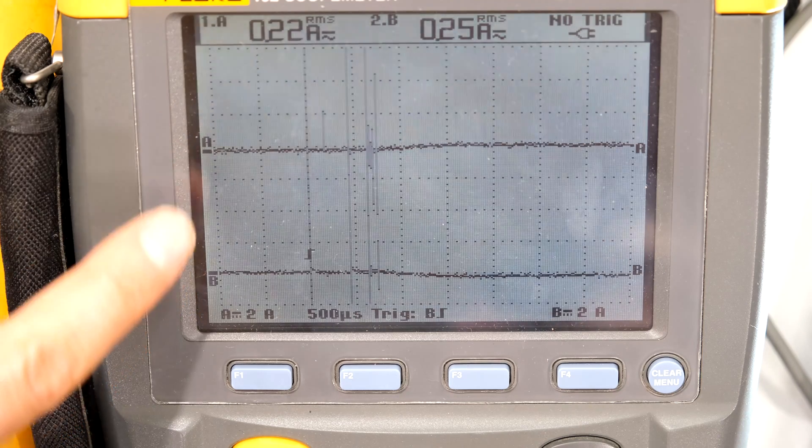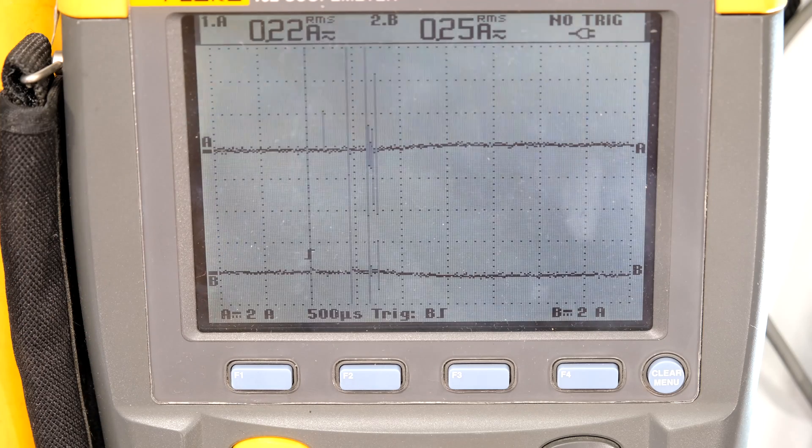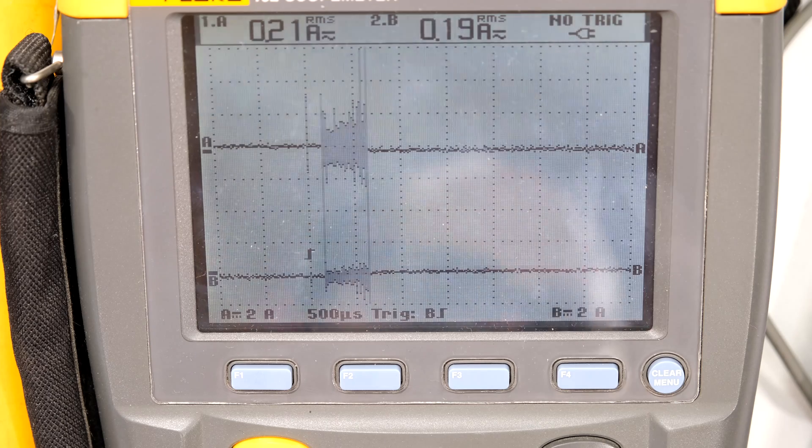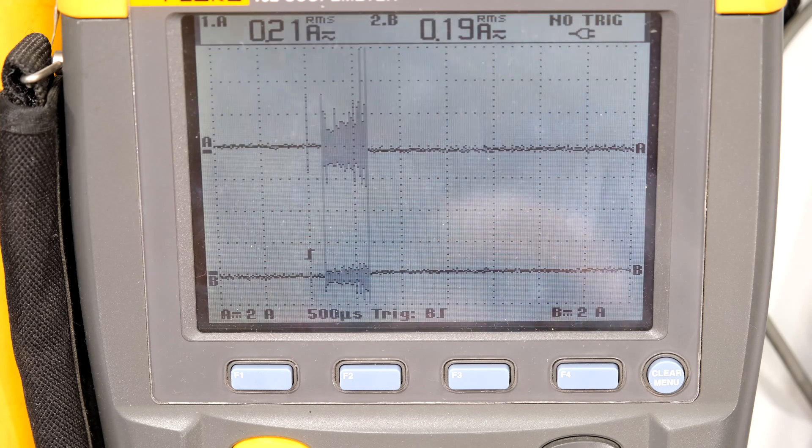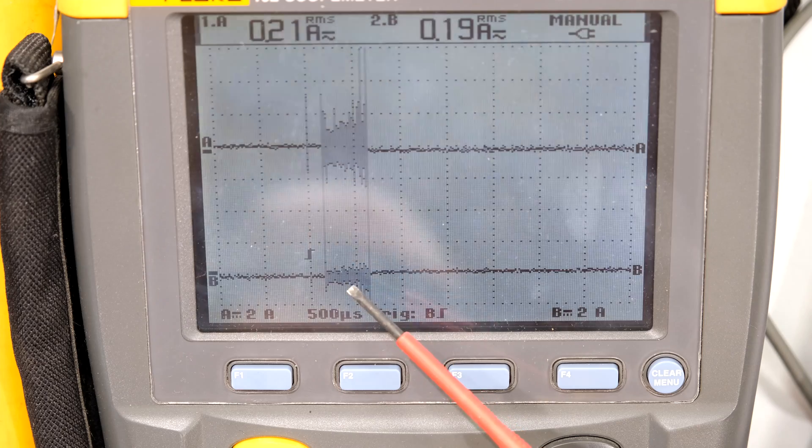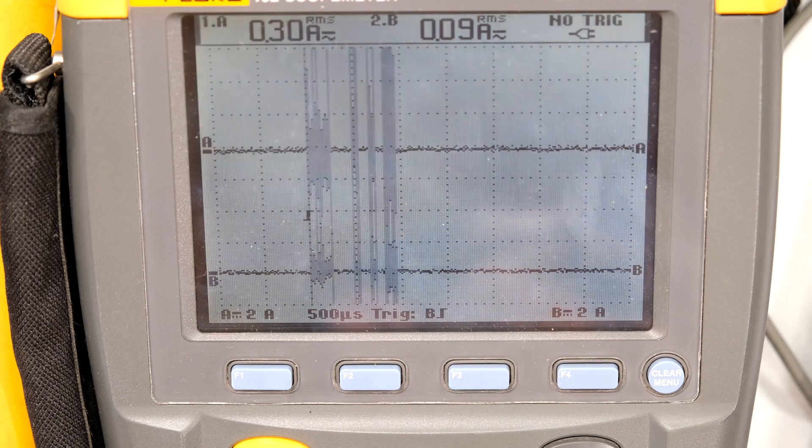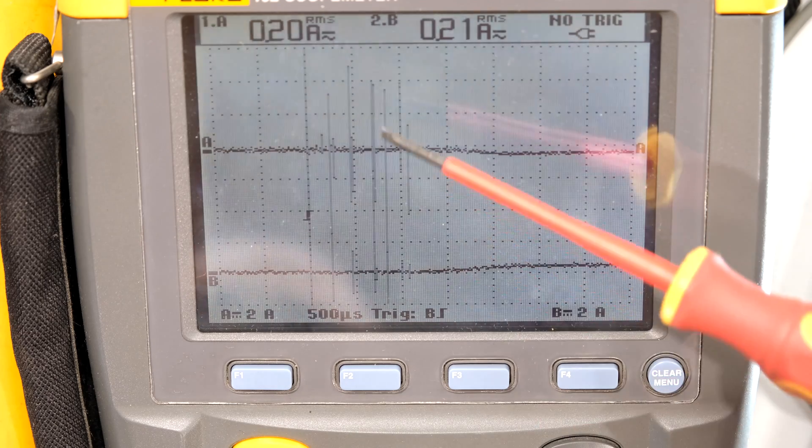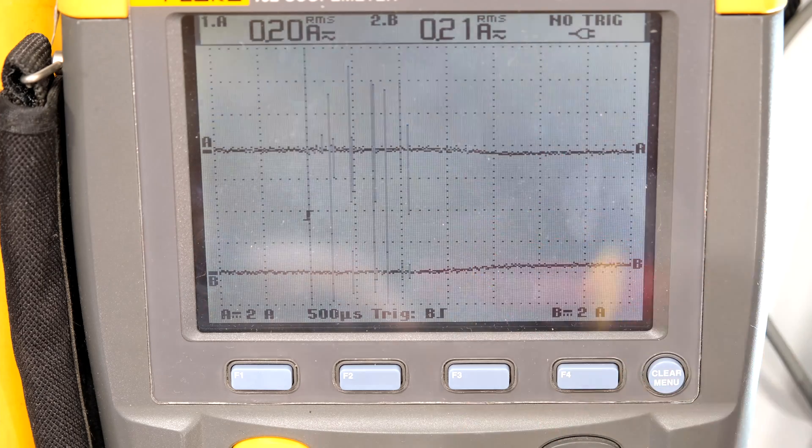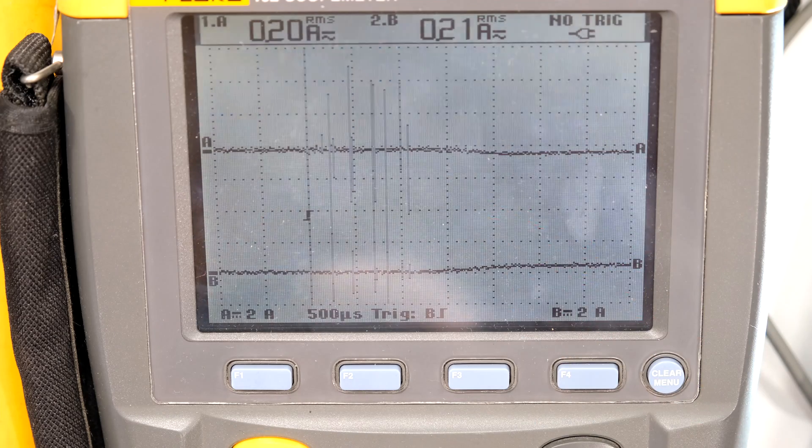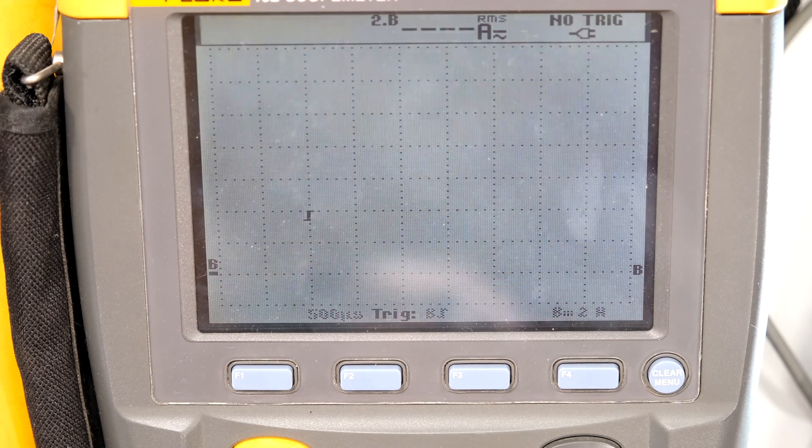Right, so there is the turn on of the lamp. The two current measurements pretty much agree with each other. The current clamp has higher noise. Remember that it also had higher noise when I was doing the regular nominal measurement. So I'm going to be focusing mostly on this wave at the bottom. I've turned on there and you can see that they pretty much agree with each other although the current clamp probably has that hysteresis, so it's a bit higher. What I'm going to do is switch off the current clamp reading for now and just use the other reading. I find it's more accurate.